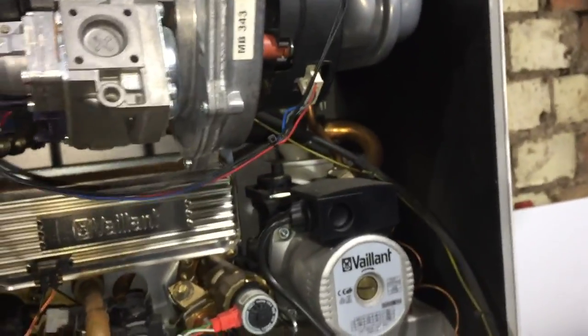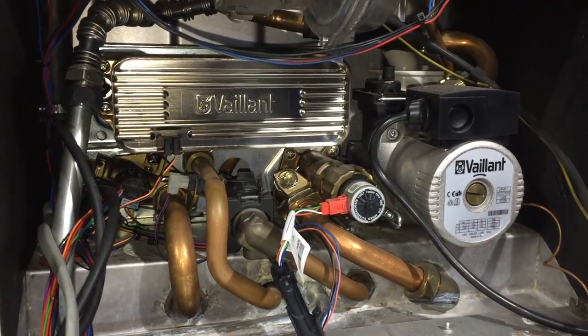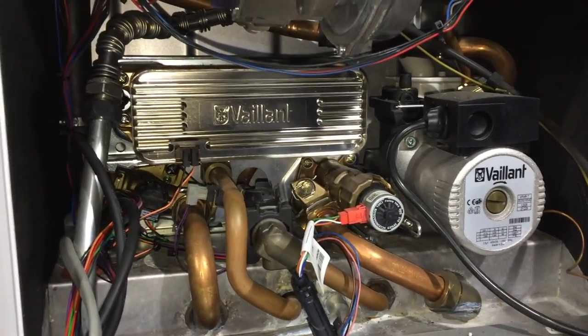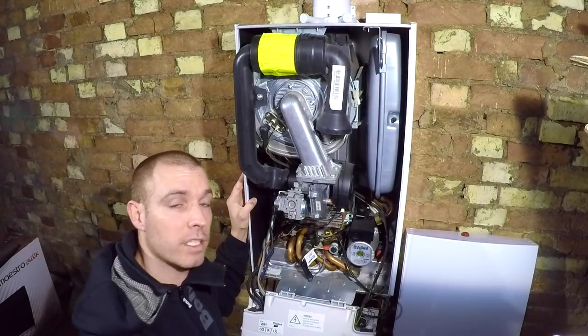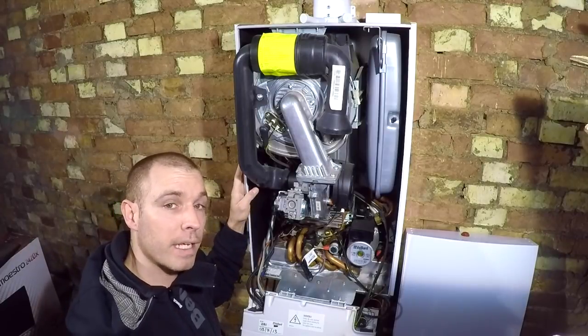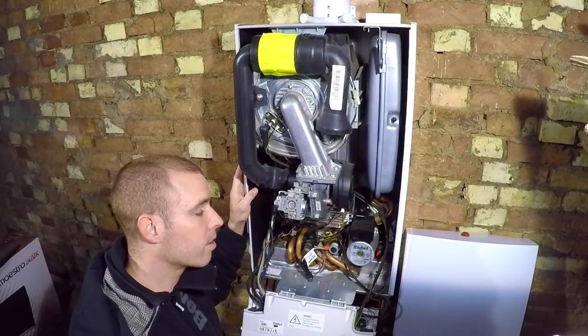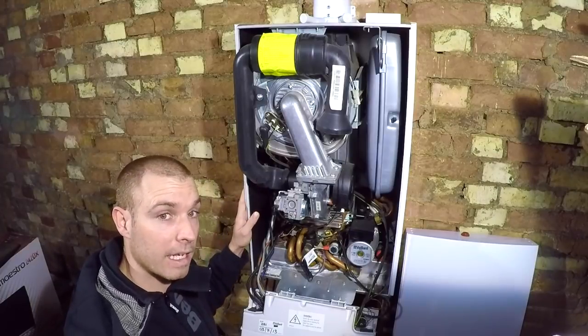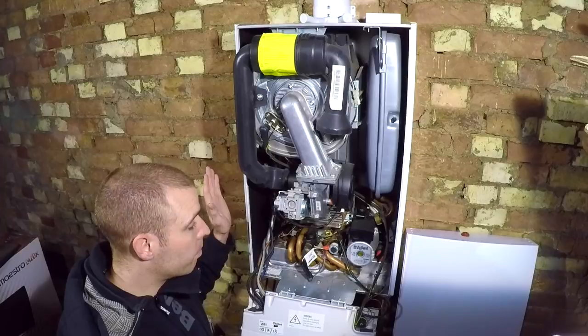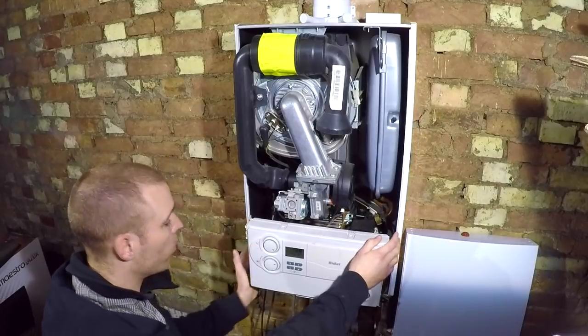So if this was a private customer, after installing this boiler they would have invested about £275 in total. That's all they would have spent in ten years on the boiler. So I'm not complaining about the longevity of this boiler. Ten years, it's never been cleaned. Hasn't got inhibitor in it - because I fitted it, then moved a radiator and drained it down within a month, and never put inhibitor back in. So this boiler: ten years, no inhibitor, and it's got a noisy heat exchanger.